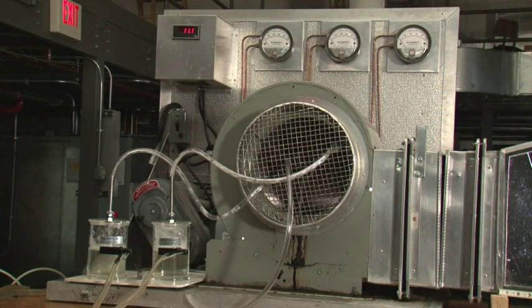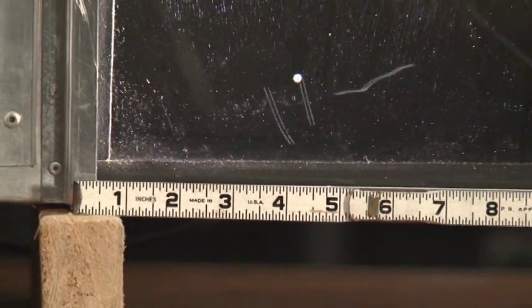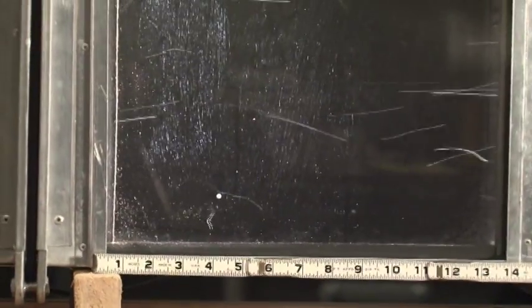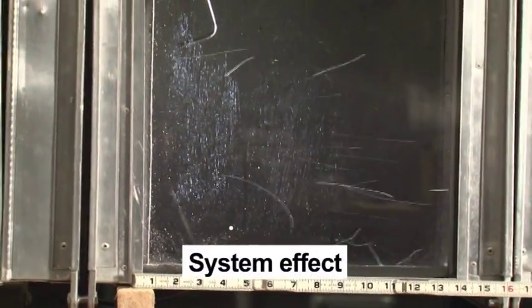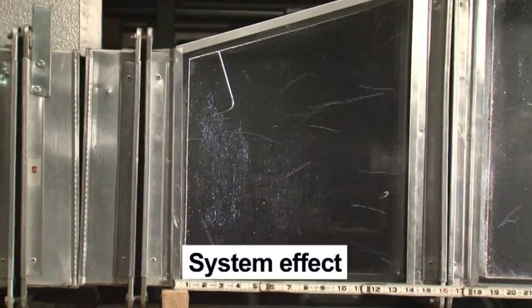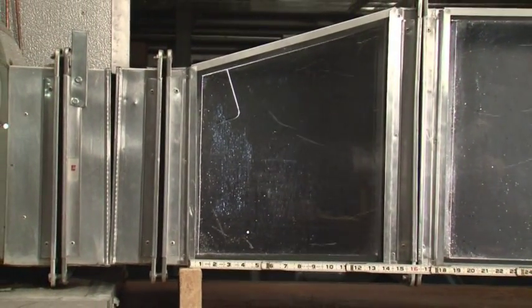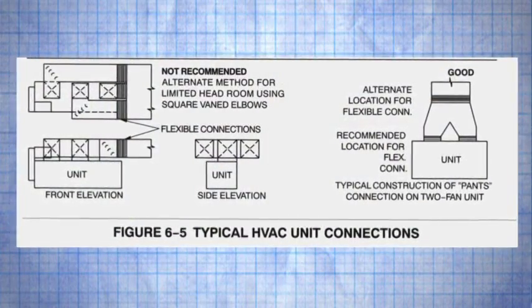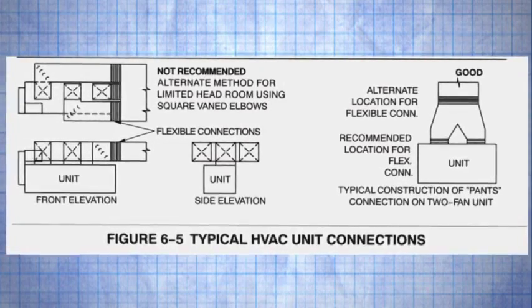Now let's begin our trip down the bubble machine's duct system. This first turbulence is near the discharge of the fan where the bubbles are moving erratically. This illustrates a phenomenon called system effect near the fan — an undesirable pressure loss that cannot be accurately calculated and is often caused by trying to make turns too quickly near the fan. Mechanical rooms that are too small are often the culprit.